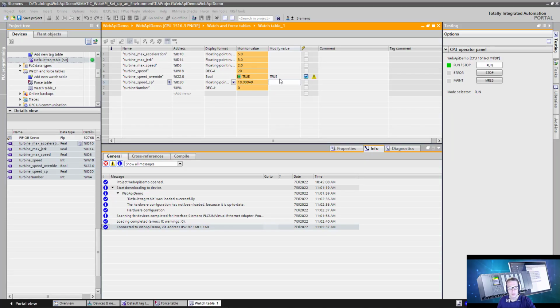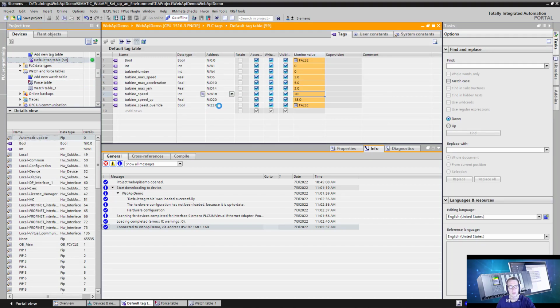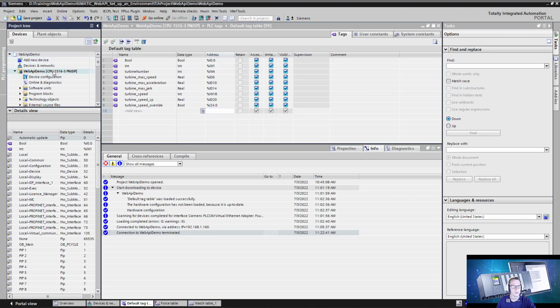Just one more thing. I had another look at the video, and I noticed that this time here I didn't calculate correctly. So the turbine speed SP with ID 20 goes to 24, and the Boolean with 22 actually is inside that range. So when changing the Boolean value, then actually this value is changed as well. And when changing this value, the Boolean might be affected. So the correct way would probably be to adjust the range for the values so that the Boolean is outside of that range. And that's basically something I wanted to add.